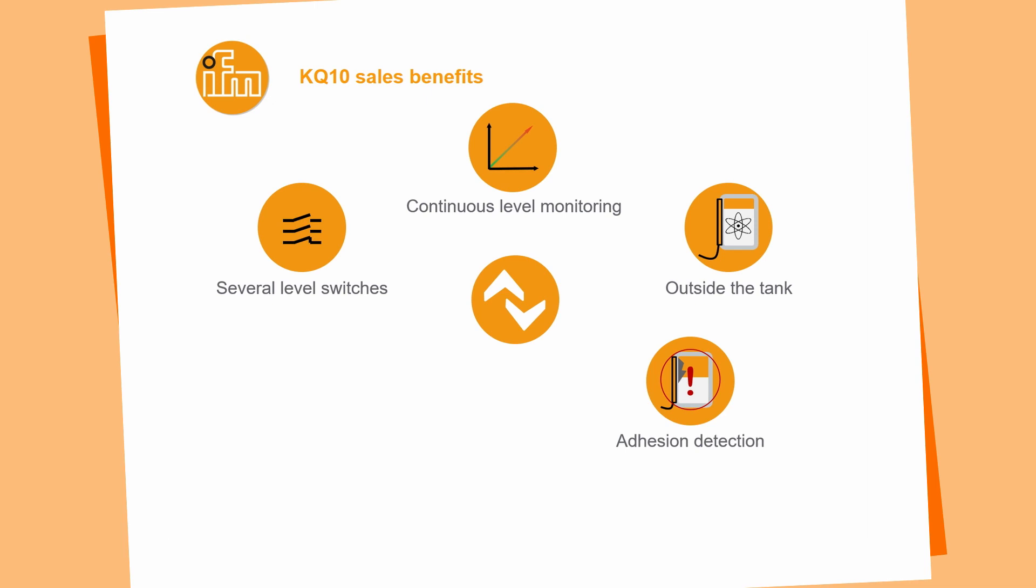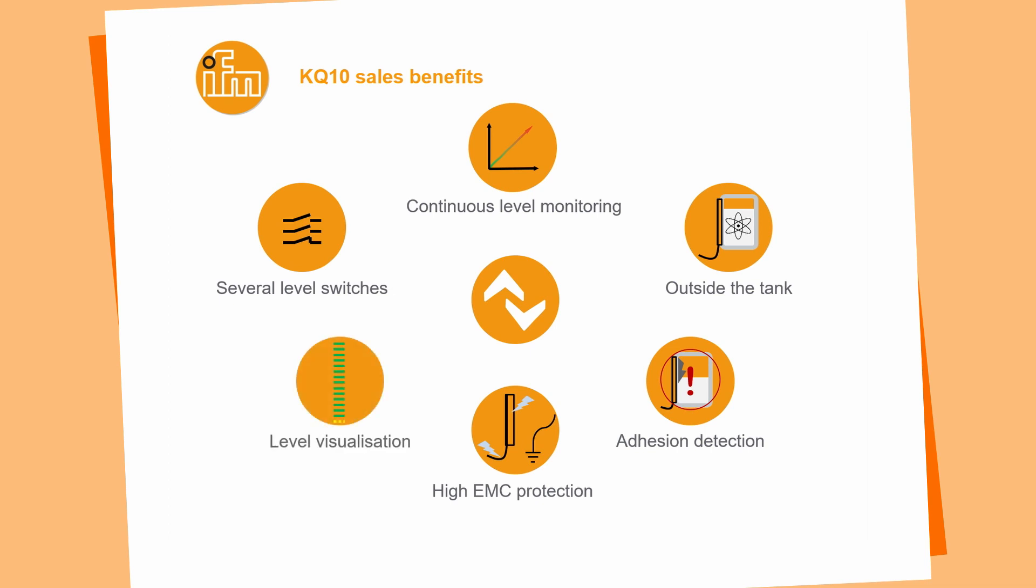We are also able to detect an adhesion. That means when you have a rising adhesion inside of your tank, the sensor is able to give you a warning, a pre-warning before an error occurred. That means in the past we had sensors which switched on and never switched off again because the adhesion was rising. This sensor is able to give you a warning before this might happen. We have a very high EMC protection. This also allows us to mount several KQ10 close to each other. It's called frequency hopping and when one sensor gets disturbed, it will switch the working frequency and will still work. The sensor shows the level inside of a tank, so you are able to see what is inside of a tank even when it's not transparent.